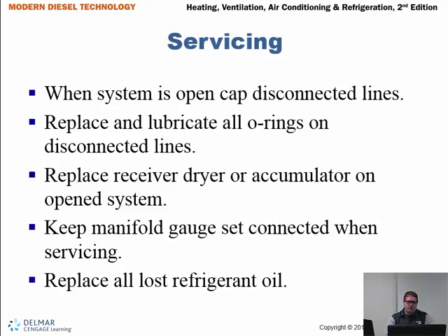And as a rule of thumb, if I don't get much refrigerant oil out of the system and I'm adding dye anyway, I will add dye with 1 ounce of oil. That's just been my preferred practice for a long time. So again, right, wrong, or otherwise, that's my practice. That's how I do that. That way, when I'm adding my dye, and we've dealt with this in class with our oil injector, adding 1/8 of an ounce of dye doesn't give the dye much medium to move around in the system.